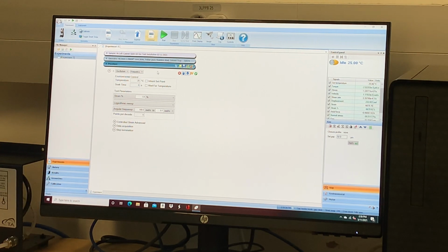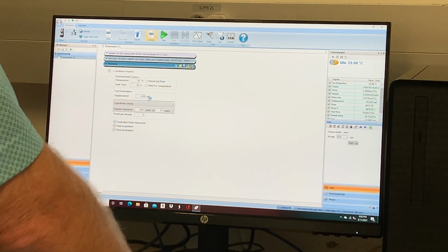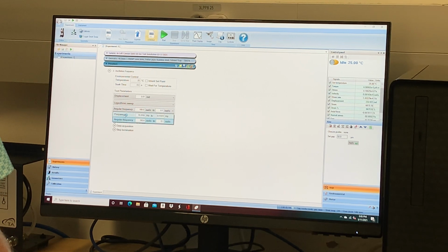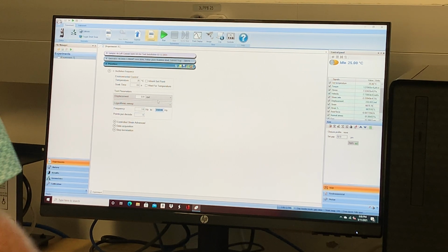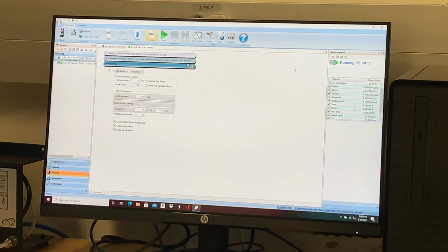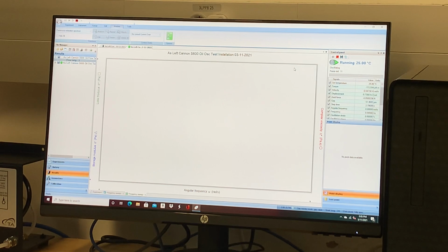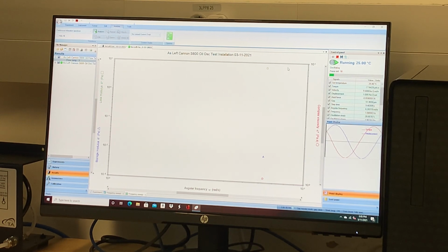We don't need to wait for temperature, we don't need a soak time. So I'm going to run a displacement, 1 to 10 hertz. And then how much data? Points per decade. Okay, so with a flow test, you're getting an actual viscosity, right? It's just like a viscometer. It's turning and it's giving you a viscosity. When you're doing an oscillation, we're looking for complex viscosity, right? So it's just doing its calculations and giving you a number.